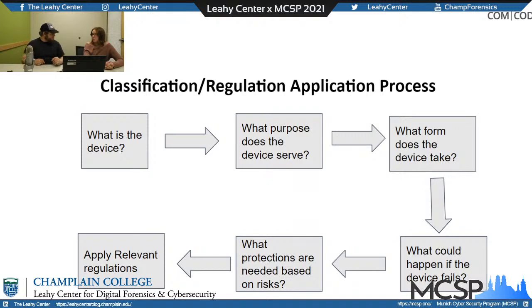Okay, so I know the government has a lot to do with regulations, but a lot of it is coming from the private scientific community and their findings, versus the government, which isn't always the best about being on top of new technology. Yes, they both take pointers from both. Even on their website, the FDA says medical devices are changing so quickly that we recommend you go to the IMDRF for the latest security, and they release guidances. These aren't hardcore requirements, but it's better if you have them.